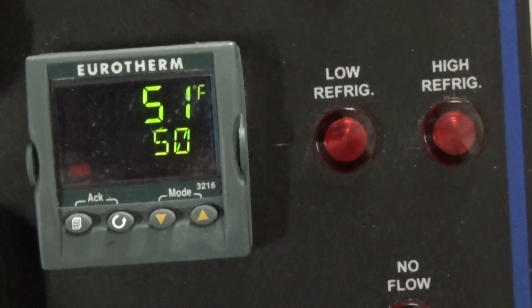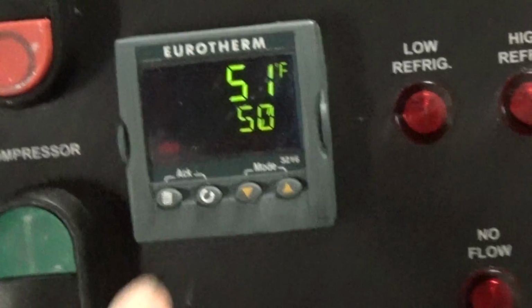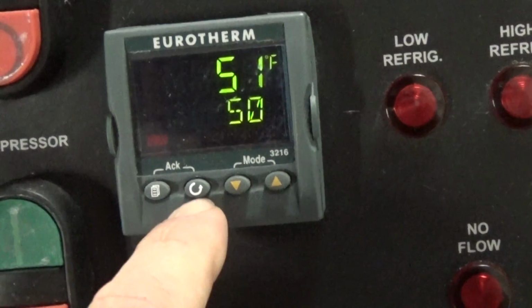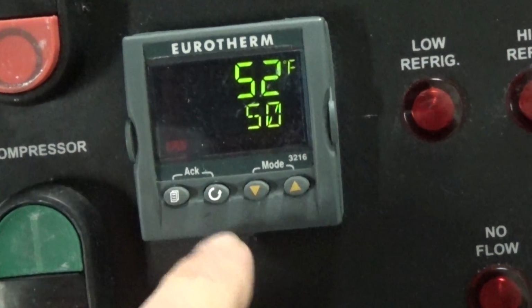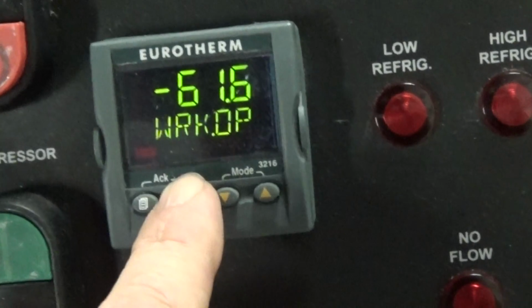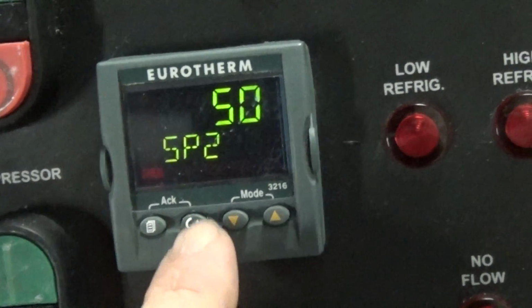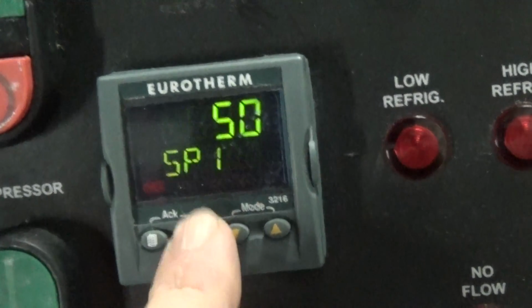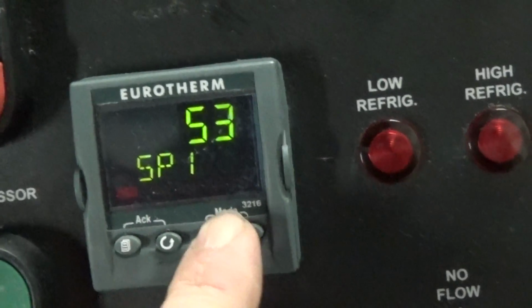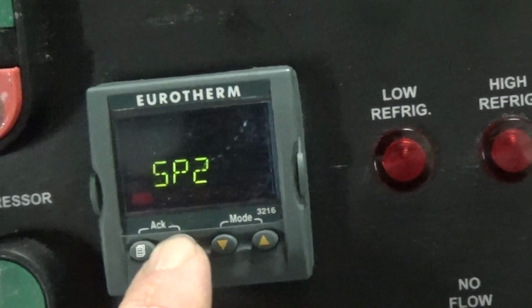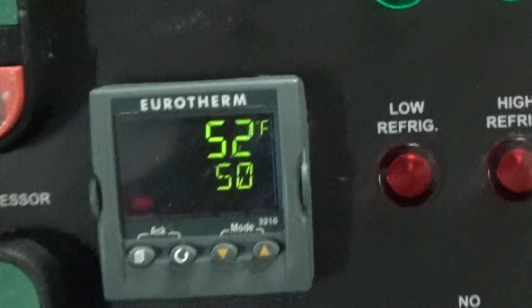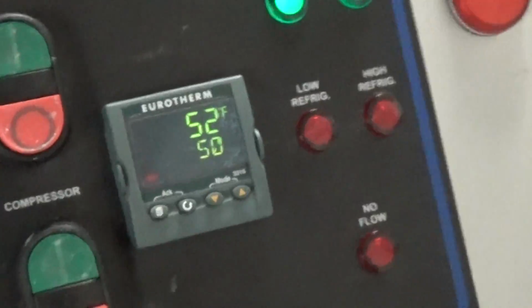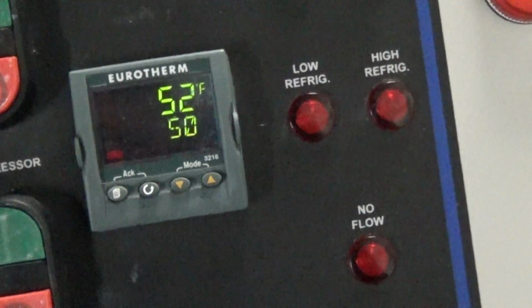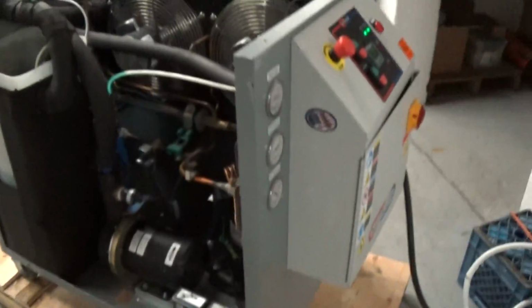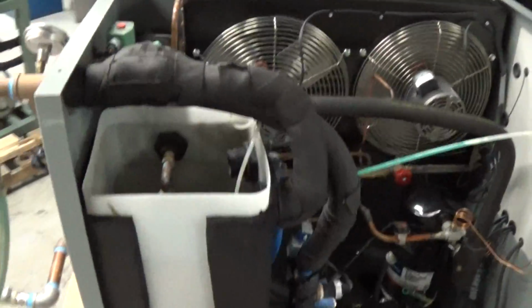But that's really all you need to worry about is this scroll circular button to get the set point 1. Don't worry about set point 2. Just go to that set point 1, and that's where you change your set point. So right now this is maintaining. We've been running it for several days. It's ready to go. We're going to get the full crate ready for the customer and post this online video.